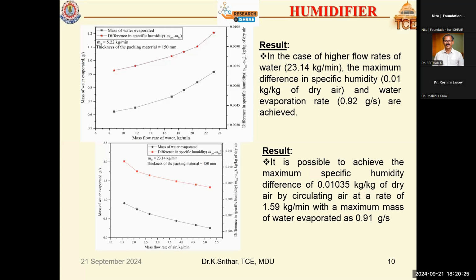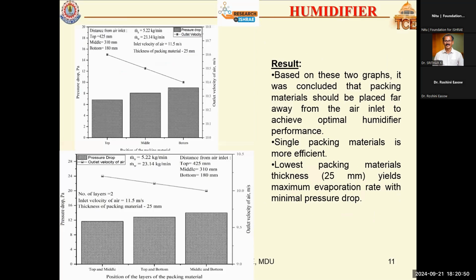So based on that, we have concluded that a higher water flow rate and a lower air flow rate are favorable for getting good results. So we have fixed this mass flow rate. And based on the mass flow rate, we have changed the thickness of the material. Actually, this experiment result is shown for a packing material thickness of 150 mm and for a single packing material. Then we have changed the packing material for different cases.